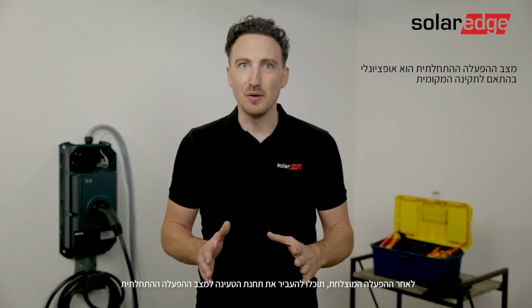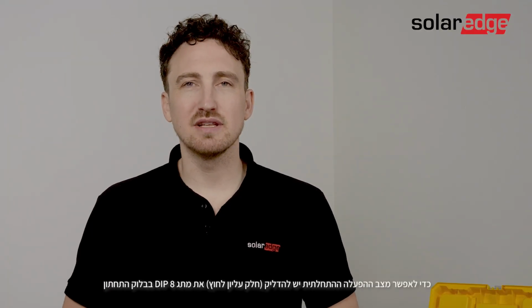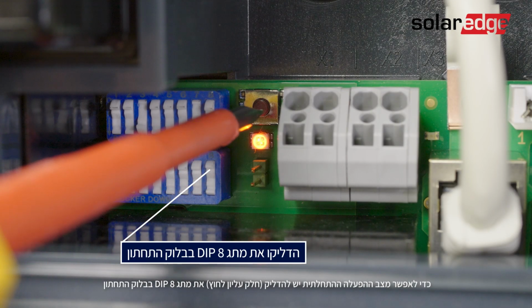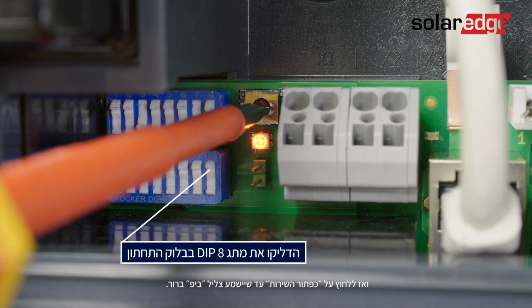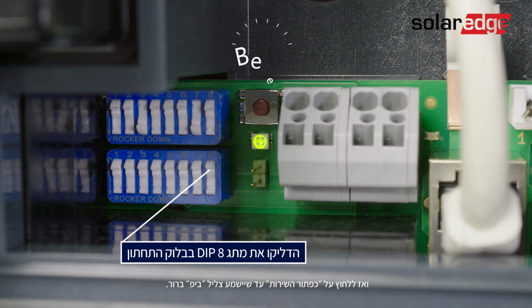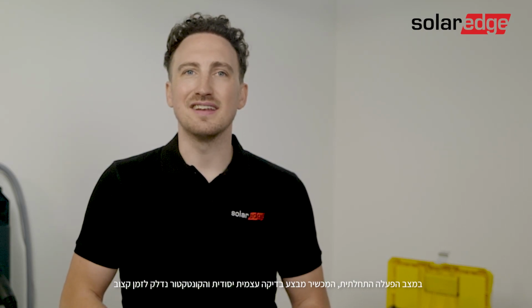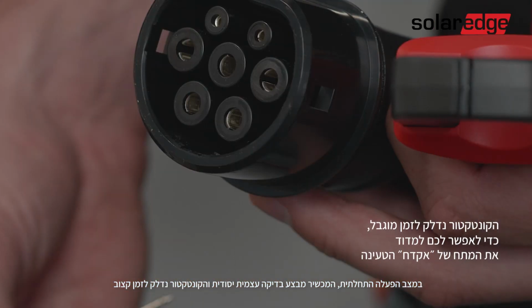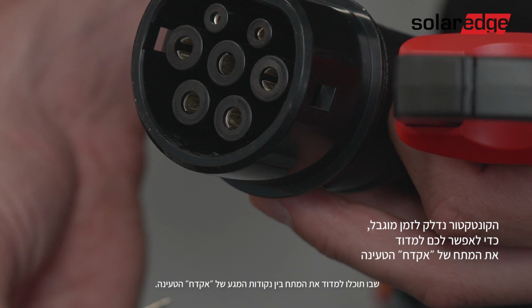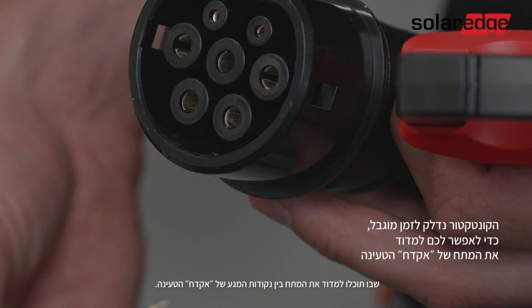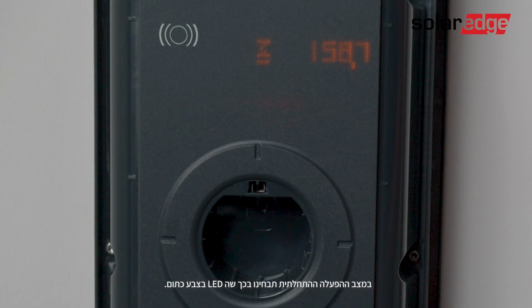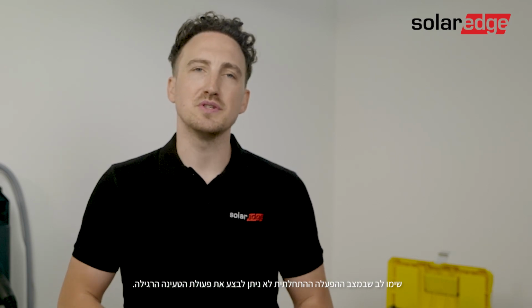After the successful startup, you can put the charging station into the commissioning mode, needed to perform the required initial testing. To activate commissioning mode, you will need to turn on dip switch number 8 in the lower block in the upwards position, and then press the service button until you hear a clear beep. In commissioning mode, the device carries out an extended self-test and the contactor is switched on with a time limit to allow you to measure the voltage on the contact points of the charger gun. Once you're in the commissioning mode, you will notice the LED turns orange. Please notice that a normal charging procedure is not possible when you're in commissioning mode.